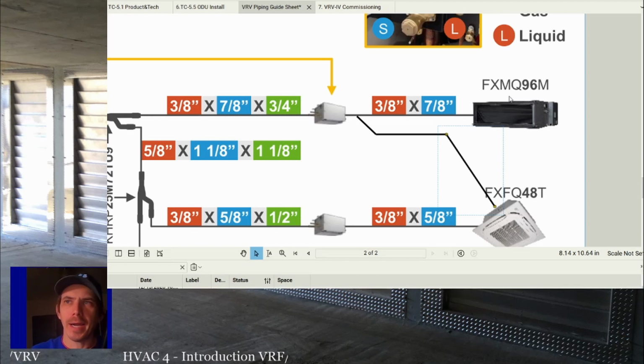So in general, I don't recommend a single branch selector serving different rooms, if at all possible. All those units should be in the same room if they're off a single branch selector. If they are going to be separate rooms, they should all be the same kind of load. So they should all be on the south wall of the building with about the same amount of windows, or all on the north wall on the outside of the building, or all on the interior of the building. You want them to have the same kind of exposure to the sun, similar construction, and basically similar needs when it comes to heating or cooling.